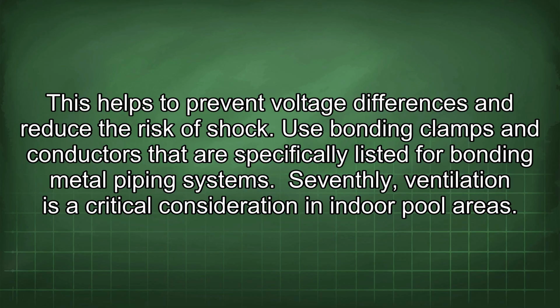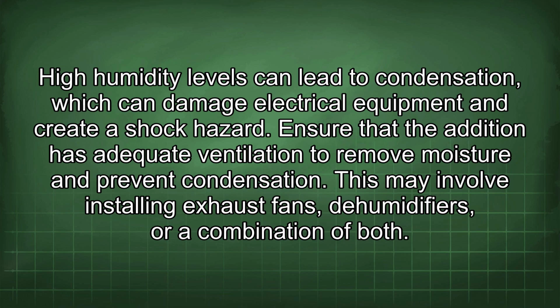Use bonding clamps and conductors that are specifically listed for bonding metal piping systems. Seventhly, ventilation is a critical consideration in indoor pool areas. High humidity levels can lead to condensation, which can damage electrical equipment and create a shock hazard. Ensure that the addition has adequate ventilation to remove moisture and prevent condensation.